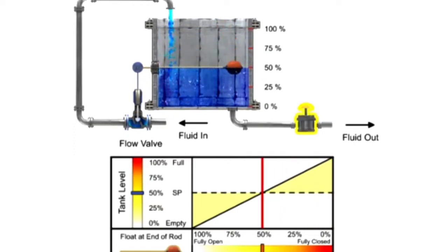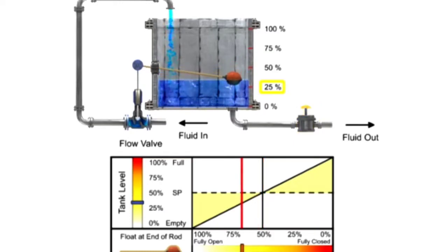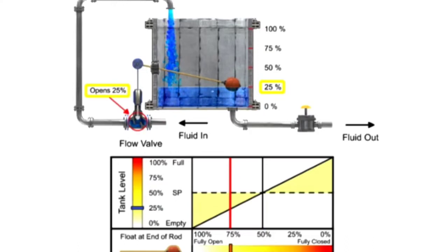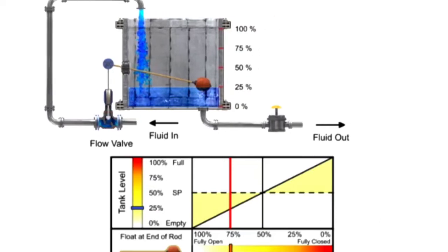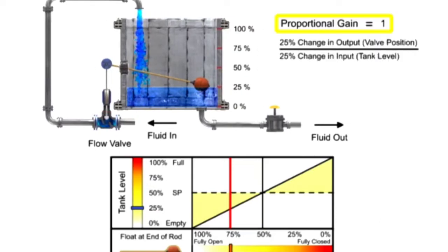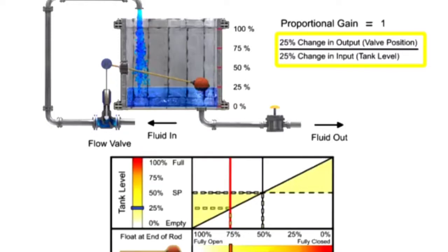Opening the drain valve increases the load demand, which causes the tank level to drop by 25%. The float drops and the valve opens 25%, which allows more fluid flow to enter the tank. A gain of 1 is demonstrated in this mechanism since the 25% change of input, or tank level, results in a 25% change of output, or valve position.